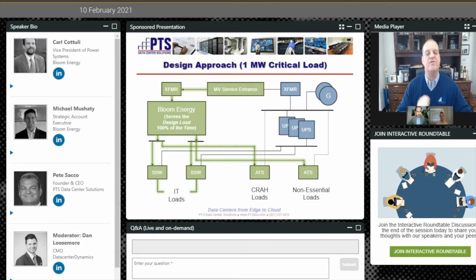Like I would in a traditional 2N design. So therefore the losses, even though those manufacturers have done a great job in the last few years to minimize the amount of losses in those systems in idle and standby, we don't have any of them because your primary energy source is going to be through the Bloom, which is highly energy efficient. So your contribution to PUE is low.